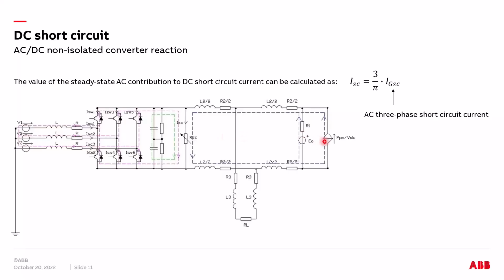And then we can also have the contribution coming from the photovoltaic system, even if, as you know, the contribution coming from the photovoltaic system is usually quite limited to a value close to the rated current of this photovoltaic system. But if the DC-DC converter installed inside our DC charger is not able to limit the fault current, we can have a huge contribution coming from all the batteries of our electric vehicles installed in parallel at that moment.